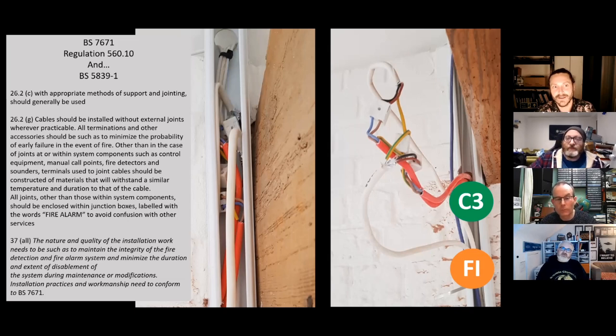Sounds like a headache, Dave. I've been to Alex and I've seen events there where they've had manual call points with conduits going up high level onto a steel frame, and then a wireless transmitter, as part of a wireless system, because when they've mapped it out, they've realized the distance to travel to an escape route needed additional measures. But that's good fire engineering practice.